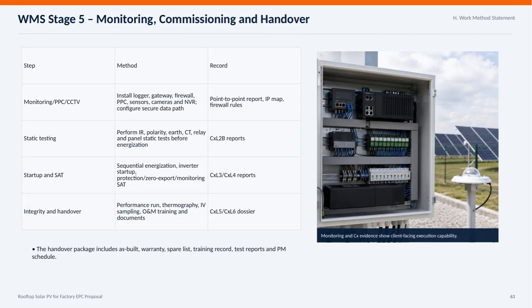At WMS Stage 5, we focus on monitoring, commissioning, and handover for the rooftop solar PV project. First, during the monitoring phase, we install key equipment like loggers, gateways, firewalls, PPC systems, sensors, cameras, and NVR units, ensuring a secure data path is configured. This allows us to generate detailed point-to-point reports, IP maps, and firewall rules.